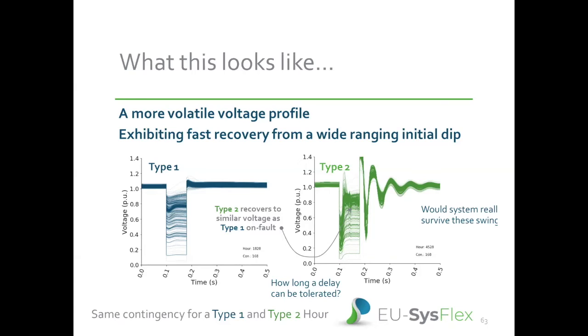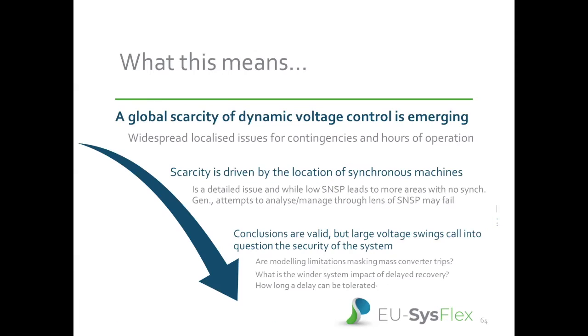After nailing down those model details, you have to think about how long a delay in that fault on recovery I could tolerate. You start, for me, then linking to a sort of FFR type conversation, but for reactive power. I don't necessarily need the instant limitation if I get very fast, controlled, dynamic reactive response that helps manage my profile, provided that fast response then doesn't give me those post-fault oscillations. So next slide, if you would, Hassan. Building on that sort of future work idea, I'm going to summarize our conclusions.